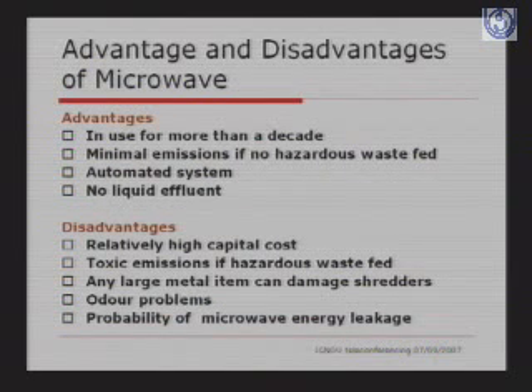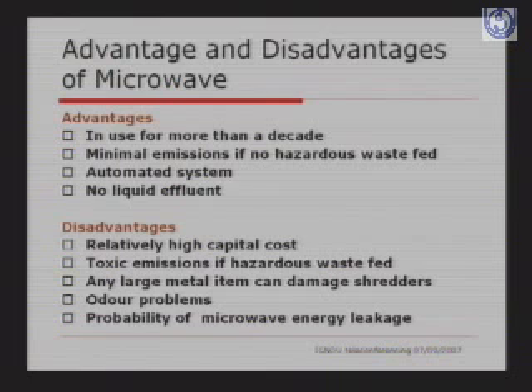The advantages and disadvantages with the microwaves. The advantages are that it's been used for many decades, as I said. Minimal emissions if no hazardous waste is fed. Automated systems, you don't have to use your hands. Like in incineration, the waste is fed frequently, and the chances of burn injuries happen when you open and check. But with autoclaves, hydroclaves and microwaves, they're automated systems, and you just have to set the cycle, the 30-minute cycle, and then you open it. And with this microwave, you have no liquid waste, that is, no liquid effluents.